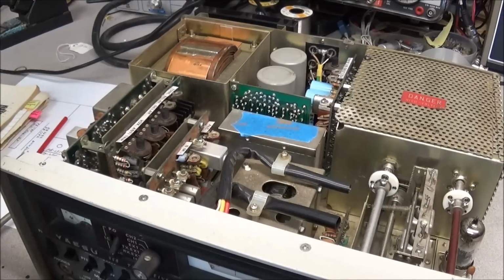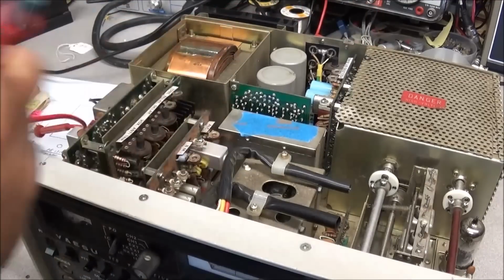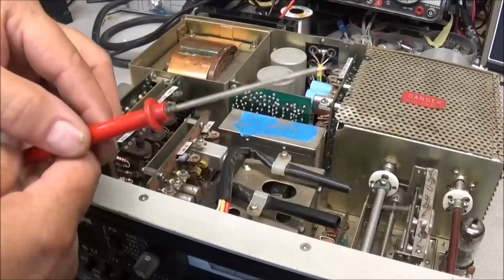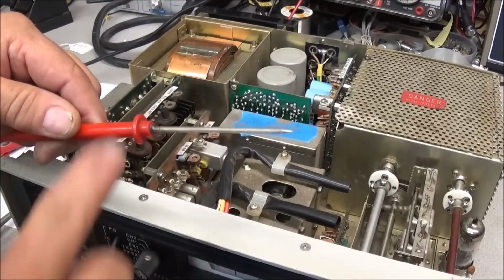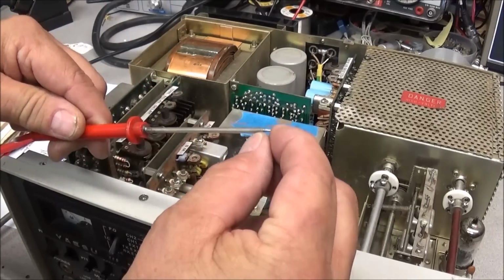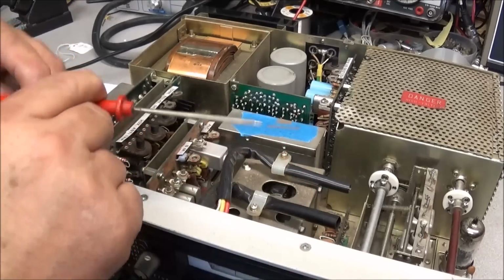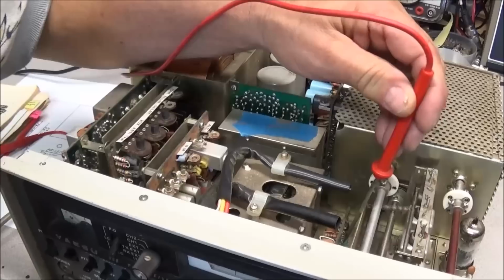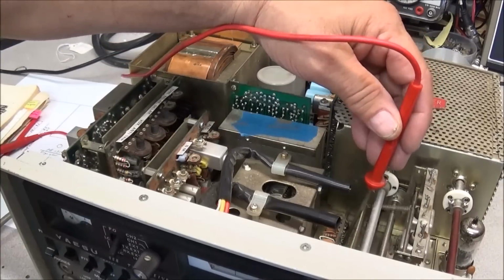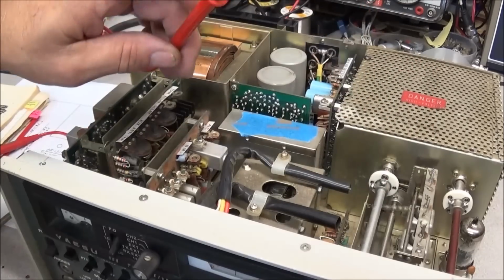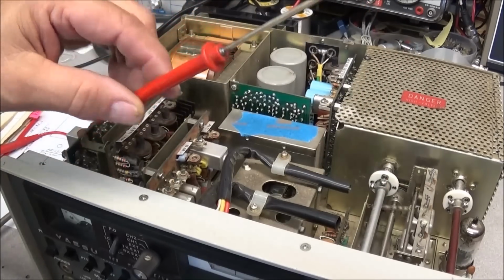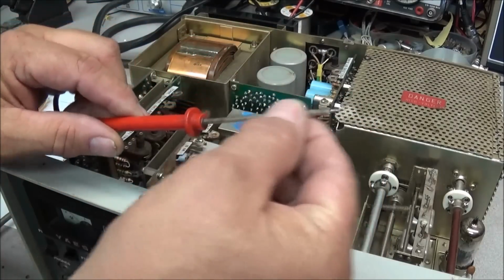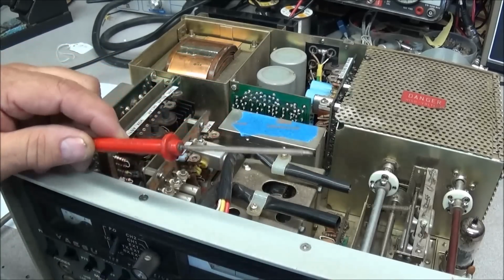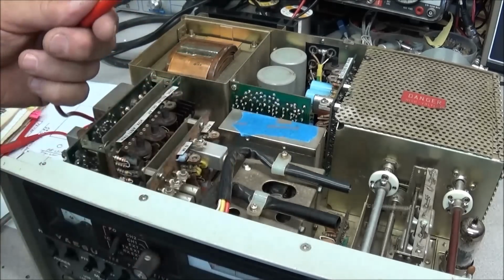Another thing, when you're doing testing, if you have a probe with a long insulated tip, so you only have exposure right on the very end, you can get down inside this thing and check the voltages on those terminals without shorting anything out. So that'll help you a whole lot. This one's actually a homemade one. I took an old probe, cut the tip off, drilled a hole into it, stuck in a tip that I needed, filed it down, brazed it in place, screwed it back in, and there we go.